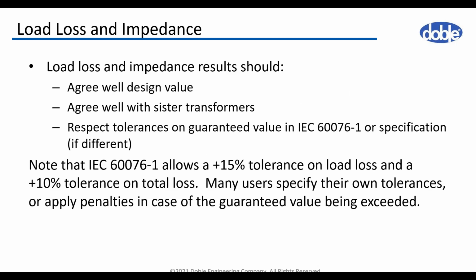As I already noted, the result should agree with the values expected from the design review, as well as with results from a sister unit if we have previous measurements. It should also respect the guaranteed values. IEC allows some tolerance for load loss and impedance, as well as the total loss, but many users specify their own limits, and if they are exceeded, then penalties apply.